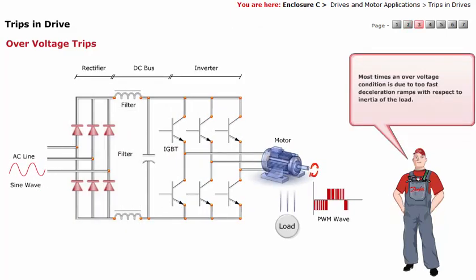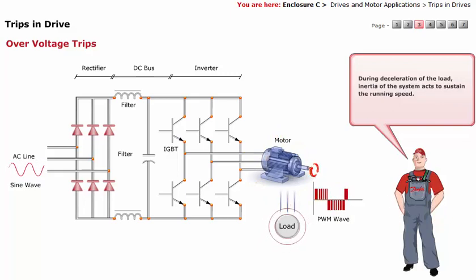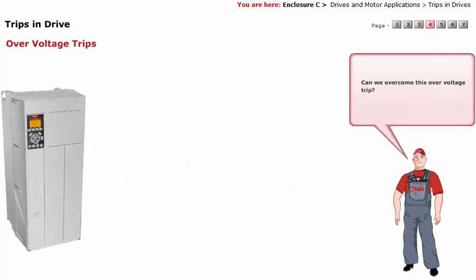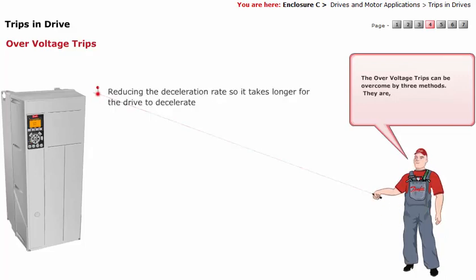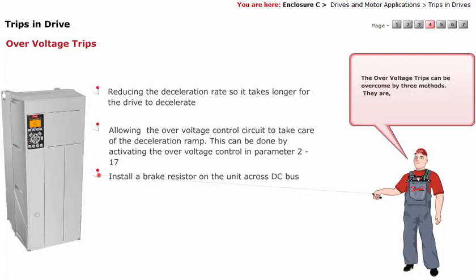Most times, an over voltage condition is due to too fast deceleration ramps with respect to the inertia of the load. During deceleration of the load, inertia of the system acts to sustain the running speed. The over voltage trips can be overcome by three methods: reducing the deceleration rate so it takes longer for the drive to decelerate; allowing the over voltage control circuit to take care of the deceleration ramp, which can be done by activating the over voltage control in parameter 217; or installing a brake resistor on the unit across the DC bus.